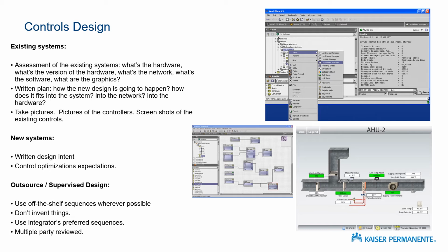So what we need to do is, during design, we need to write down as much as we can. If there's not a controls guy on board, then we really need to assess the system as much as we can. When my team sees a single paragraph or a single line that just says, expand the existing control system, that's a red flag for us. For existing systems, we want to see an assessment of the existing system. What is the hardware? What's the version of the hardware? What's the software? What are the graphics?